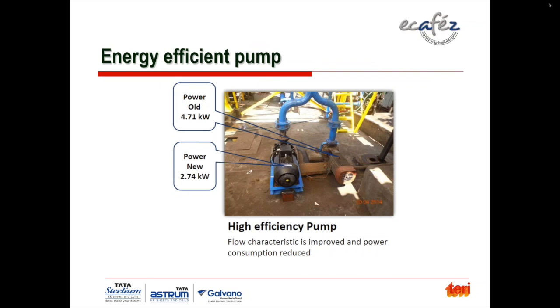Now, a simple thing like a pump could save a huge amount of energy. As you can see, this particular factory has two pumps side by side, the new pump and the old pump. What was wrong with the old pump? Basically, it had high energy consumption. It was an old pump, 7.5 horsepower, with a design efficiency of 37%, and operating at only 25%. We measured it during the audit.